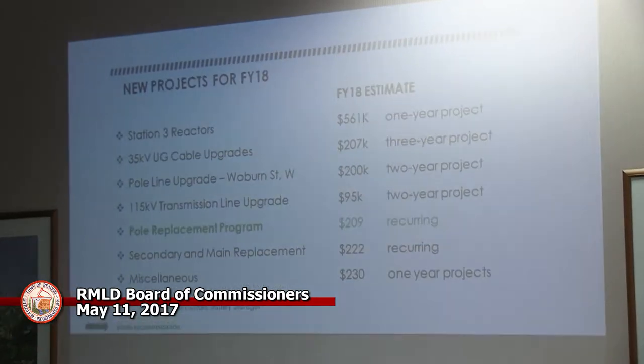So this is the Station 3 reactor project, part of the design for that substation to lower the incident energy and arc energy. To compensate for the transformer impedance, we are installing these reactors, six in total, one set for each transformer, to drop the incident energy and make it safer.